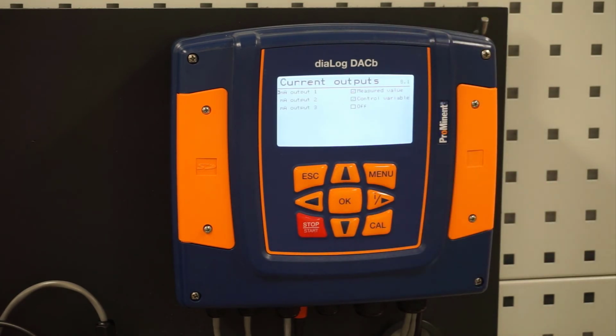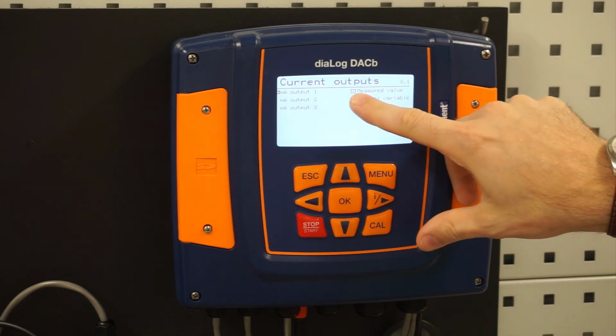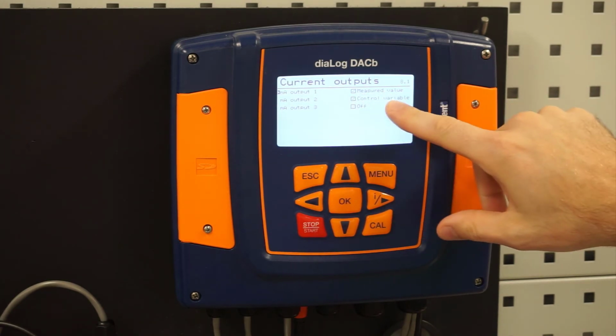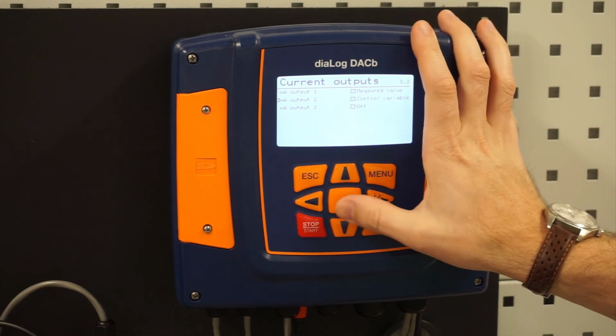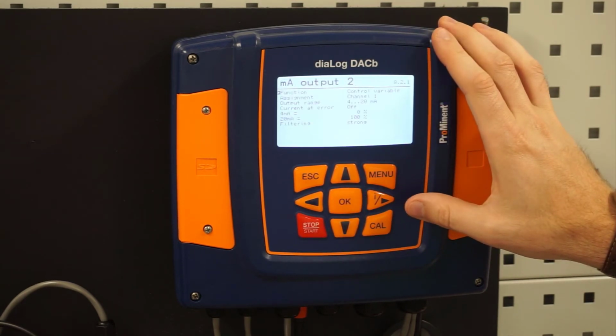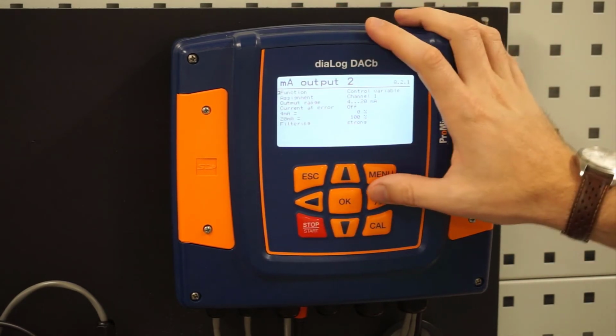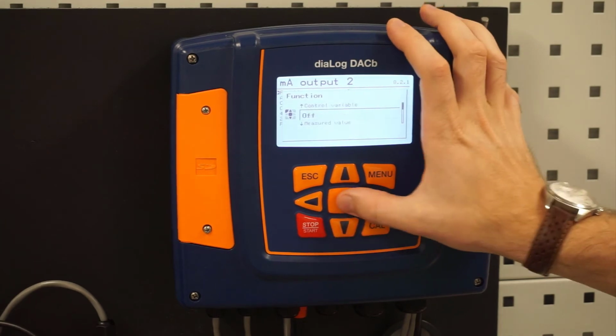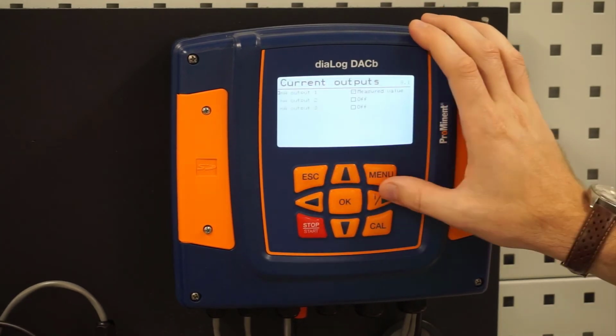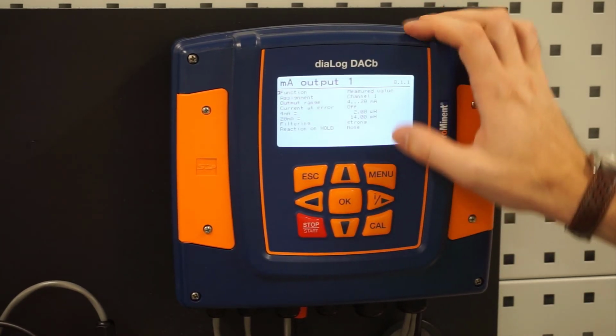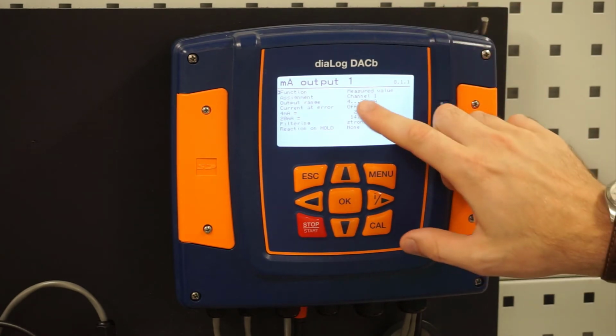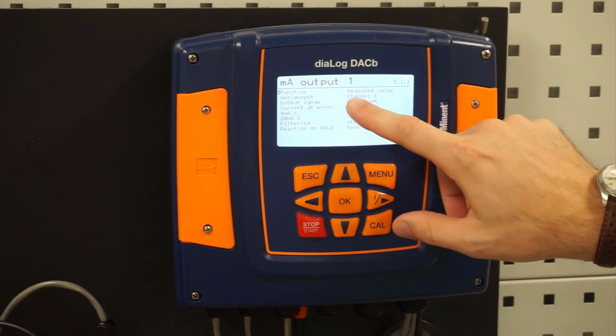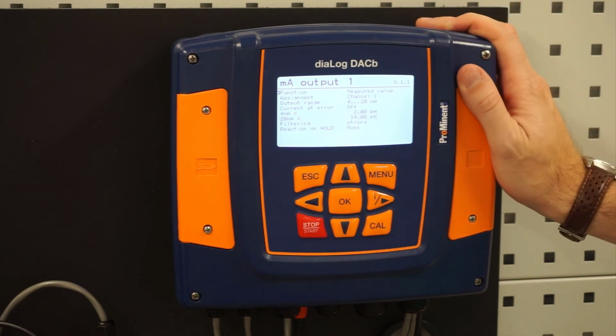Next thing is your current outputs. Remember, we have 3 milliamp outputs. In this case, we are using 1 as a measured variable and 1 as a controlled variable. Let's go to our control variable. It's not set up to do anything, so let's disable it. Okay. Let's go to output 1. So output 1 right now is set up as a measured variable on channel 1, so that's our pH.